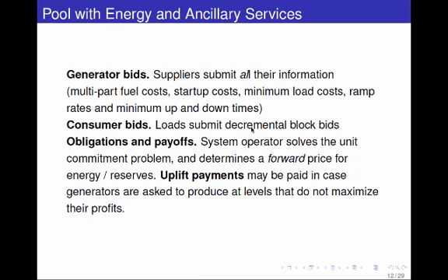They're basically asked to bid everything they can say about their generator. Fuel costs, block bids, your minimum load costs, your startup costs, your ramp rates, your minimum up and down times, all the data that the system operator needs to run a unit commitment, the suppliers are asked to bid it.